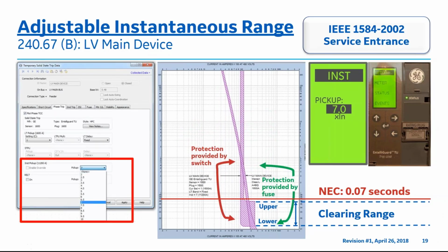From the instantaneous pickup range pull-down menu, 7.0 is selected as the instantaneous pickup value, which is also shown on the green screen on the right. Again, the setting shifted the composite instantaneous time current curve from the left to the right as the pickup was increased from 2.0 to 7.0, still meeting the 0.07 second arcing current clearing time requirement by the electronic device.